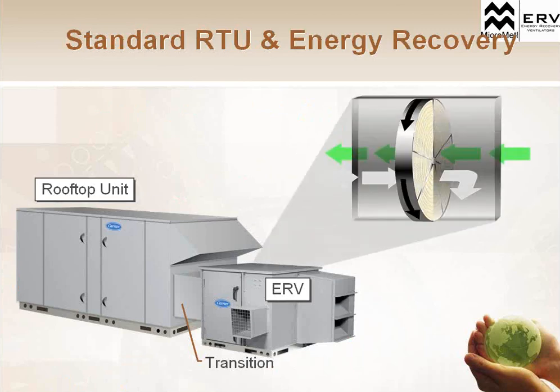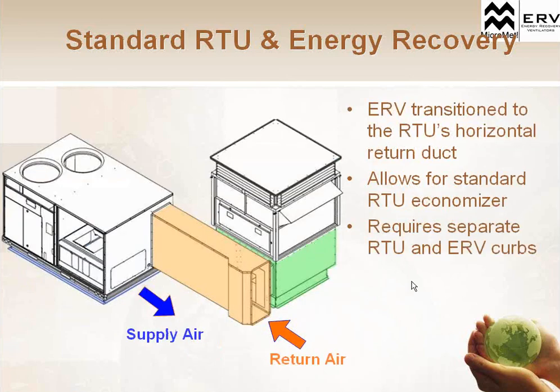The standard installation is with a packaged rooftop unit and an energy recovery unit ducted together. There's a lot of different ways that we can do that ducting, but here is what it would typically look like, a horizontally ducted system. So we have our exhaust air, return air coming out of the rooftop unit through the ERV, our fresh supply air coming in across the heat exchanger and that ERV into the rooftop unit to be fully conditioned for the space load.